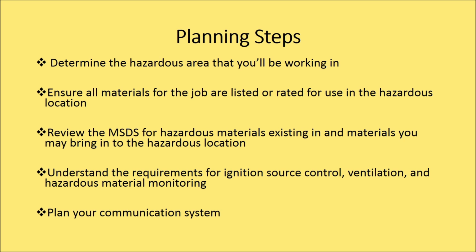This includes breakers, switches, motors, motor controllers, fuses, receptacles, fittings and boxes. Review the MSDS for hazardous materials existing in the work area, as well as any materials you bring into the work area from off-site. Make sure that you understand the handling and disposal rules for those materials. Understand the requirements for ignition source control, ventilation and hazardous material monitoring.